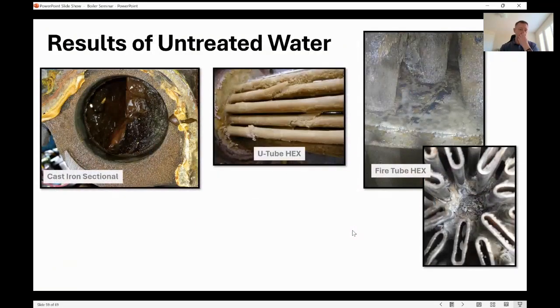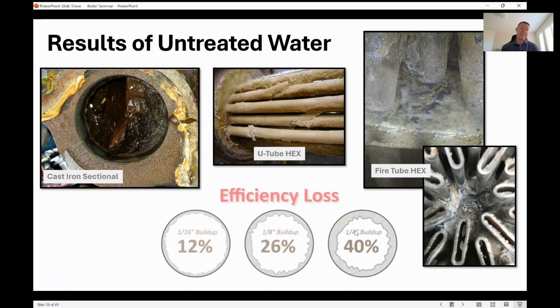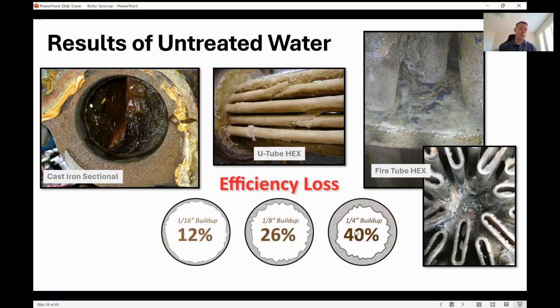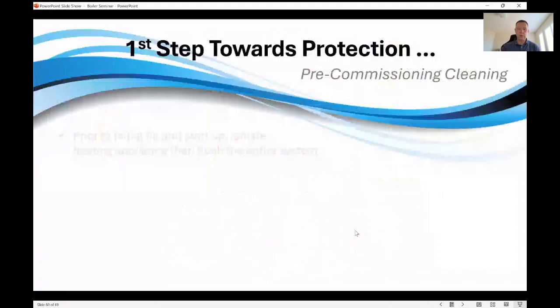So untreated water is bad, especially if you have leaks or anything like that. Because with untreated water, you're taking on new fresh water that brings in more scale into that solution. As I said, when you heat water, scale precipitates out. When there's a heat source there, it adheres to it. It forms a hard brick-like substance, which one is a fantastic insulator. So you're less and less efficient every day. And two, it's expanding and contracting at a different rate. It's causing uneven heat transfer in your heat exchanger, and that heat exchanger is going to fail much, much quicker. So you definitely want to avoid that.